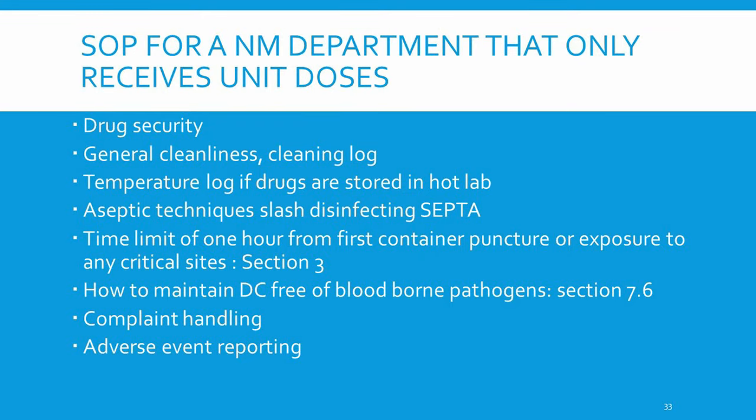An SOP for a nuclear medicine department that only receives unit doses — this should be the bulk of most nuclear departments where the pharmacy brings all unit doses and each unit dose goes to one patient. Requirements include: drug security, general cleanliness, cleaning logs, temperature logs if drugs are stored, aseptic techniques and disinfecting of septa, one-hour time limits from first container puncture or exposure to critical sites, and how to maintain the dose calibrator free of bloodborne pathogens.